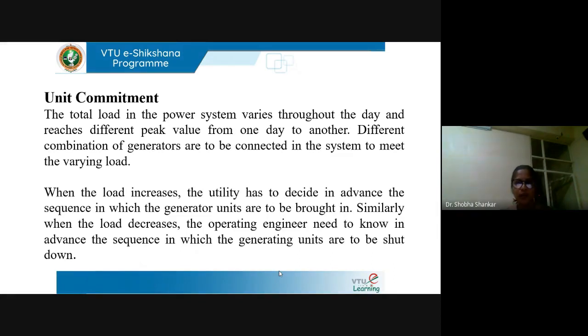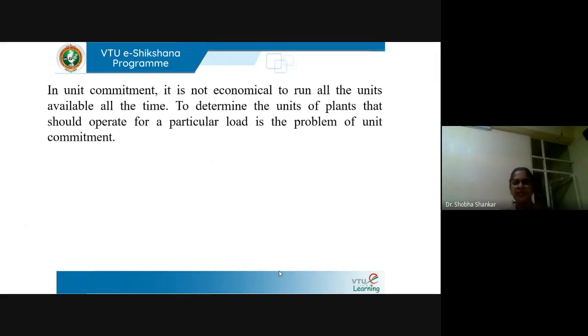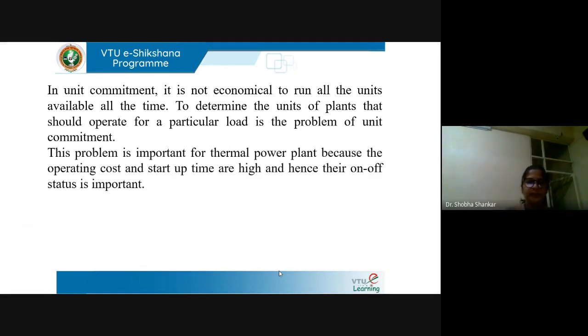When the load increases, the utility or the operating engineer should decide in advance the sequence in which the generator units are to be started. Similarly, when the load decreases, the operating engineer should also know in advance the sequence in which the generating units are to be shut down. In unit commitment, it is not economical to run all the units available all the time, so we need to determine the units in a given plant that should operate for a particular load. This problem is important for thermal plants because the operating cost and startup time are very high and their on/off status is important.